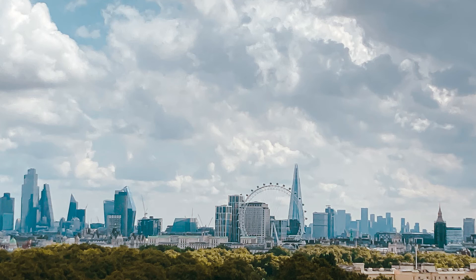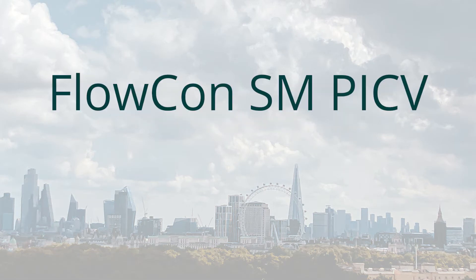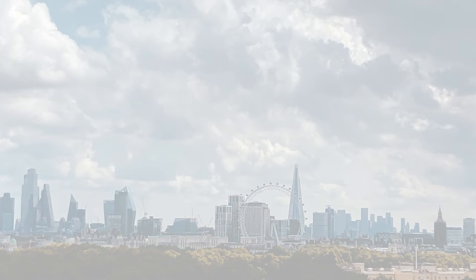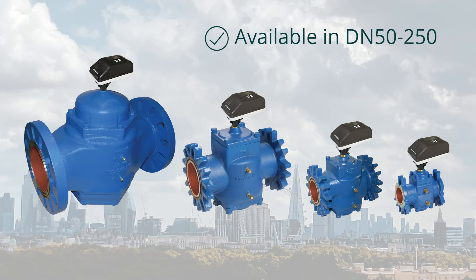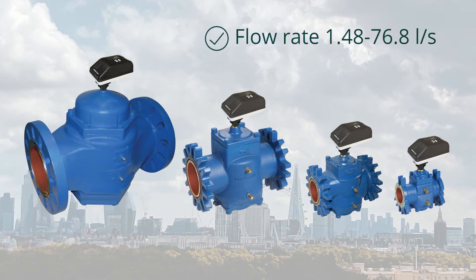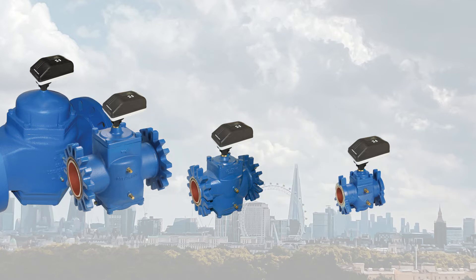Let us reacquaint you with the world's most advanced universal flange PICV — the well-proven FlowCon SM PICV, used globally for over 28 years. Available in DN50 to DN250, pressure rated PN40, with a differential pressure range of 30 to 800 kPa and flow rate of 1.48 to 76.8 litres per second.